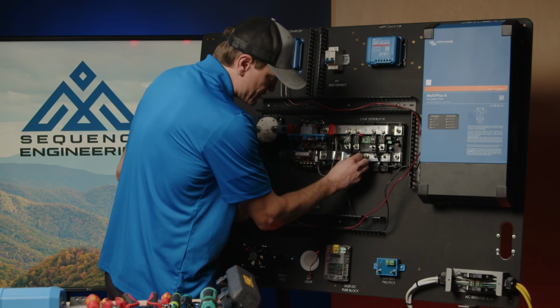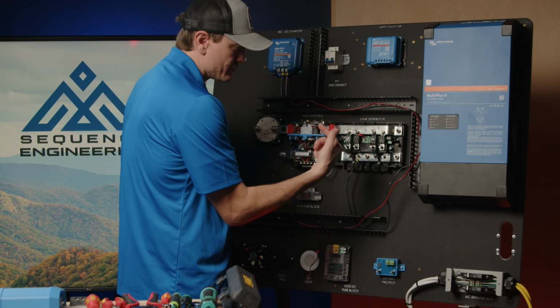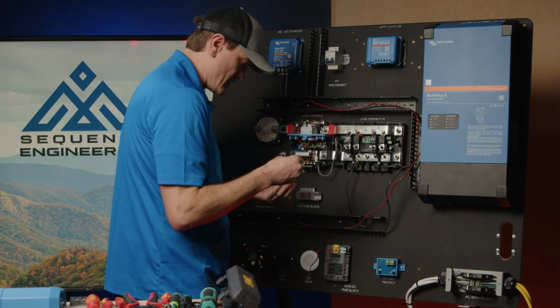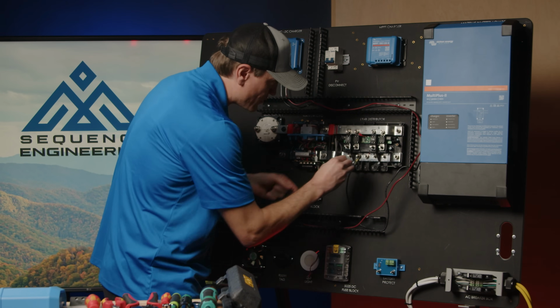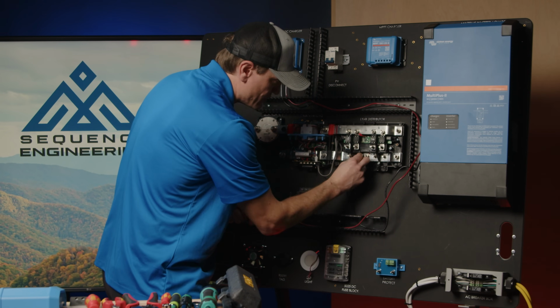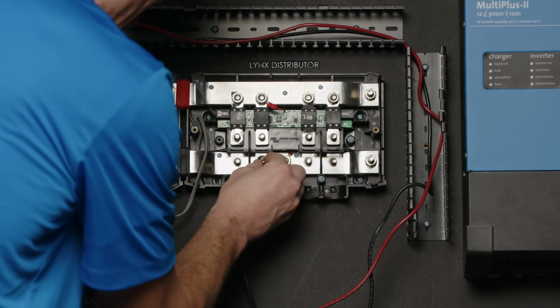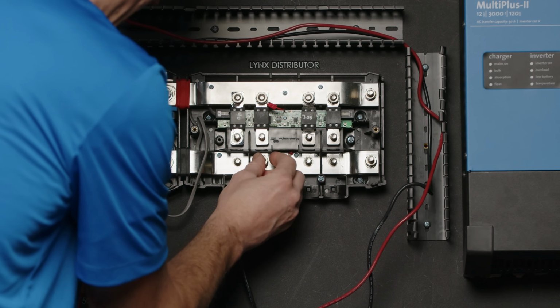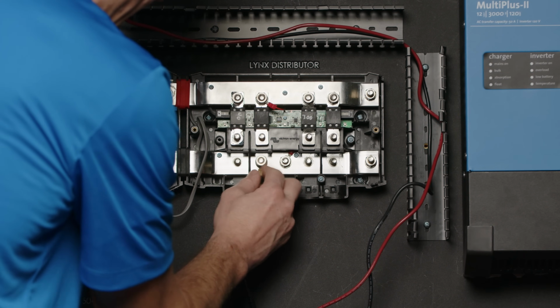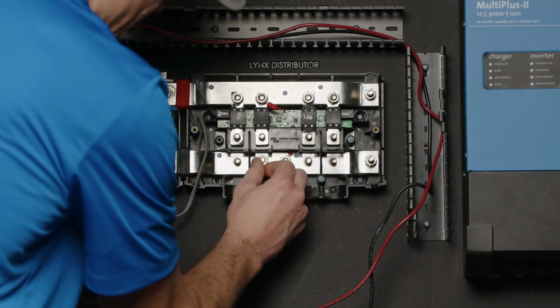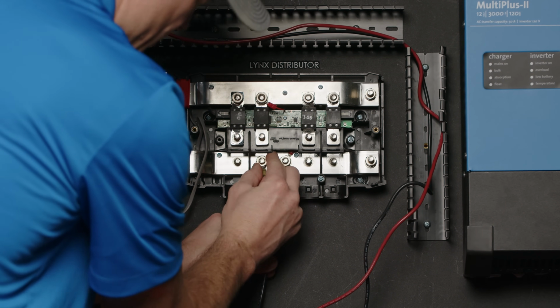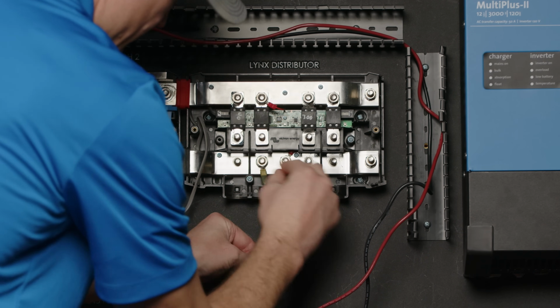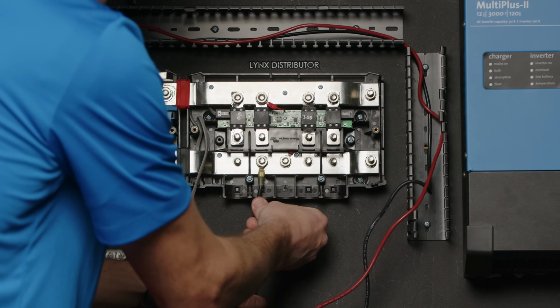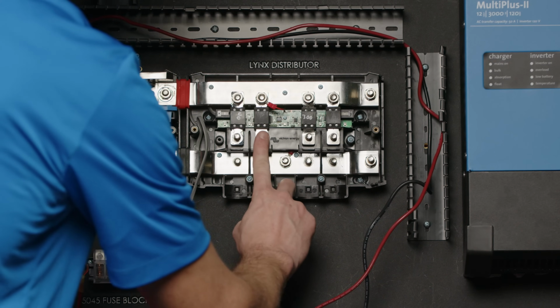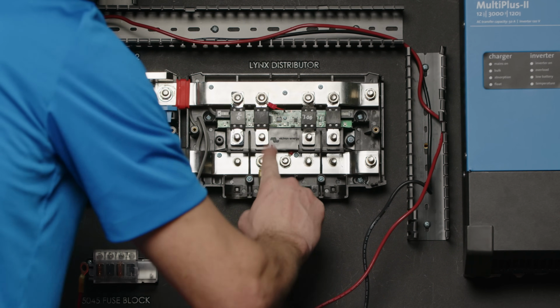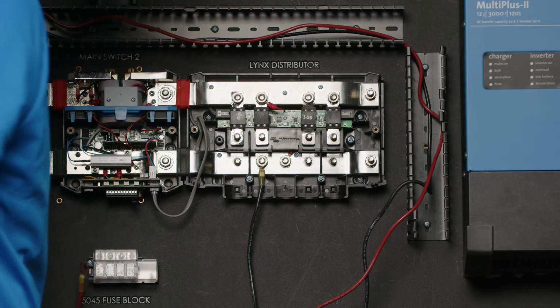Okay, washer first. Never ever put a washer between the lug and where the bus bar is positioned. Washer first, then lock washer, then your M8 nut. You can snug that up by hand, and then you'll want to go ahead and finish torquing that connection to spec, because your positive wire coming over top of that will actually prevent you from accessing that nut.